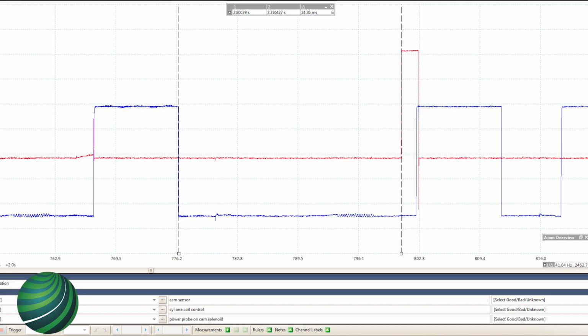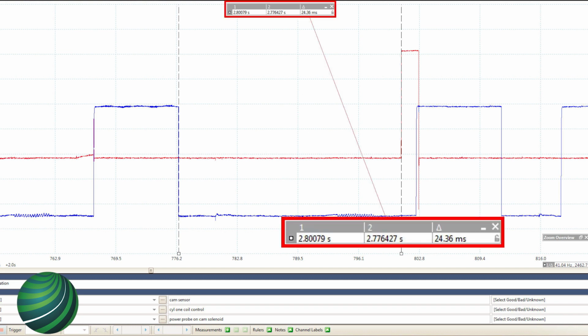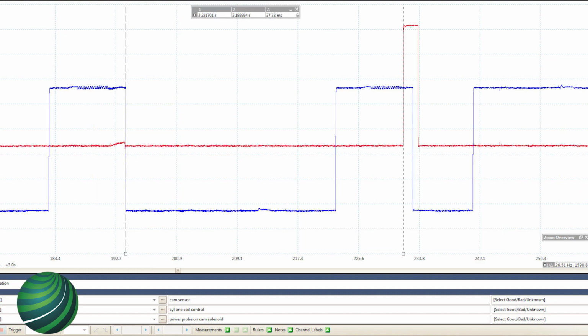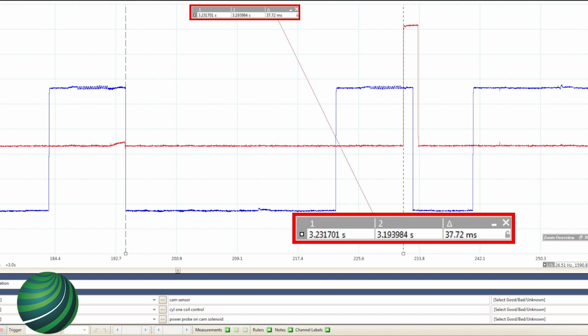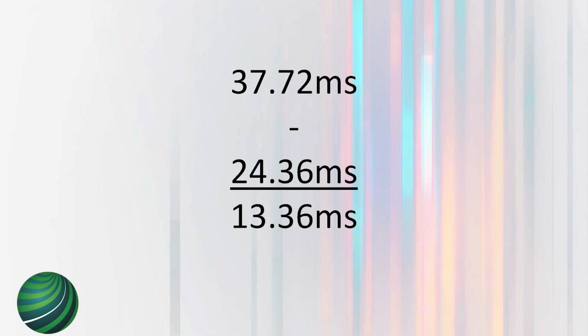So what you're going to do is do the same measurement. We're going to measure before an adjustment event just like we did before. You can see this one: we've got 24.36 milliseconds between your cursors. We're going to take a measure from after your adjustment. You can see you got 37.72 milliseconds. 37.72 milliseconds minus 24.3 milliseconds gives you 13.3 milliseconds. What's that mean?